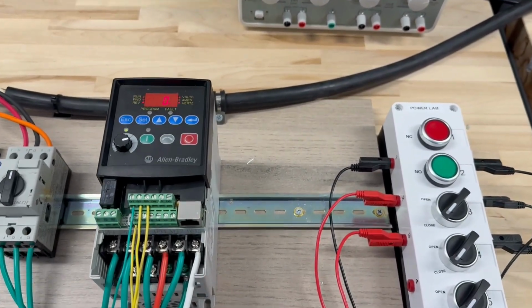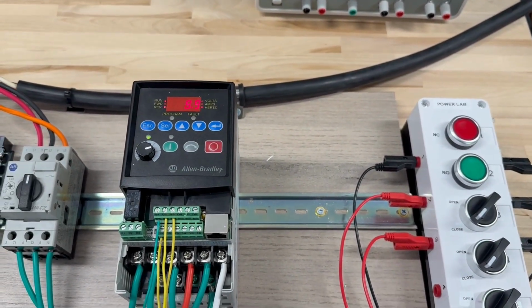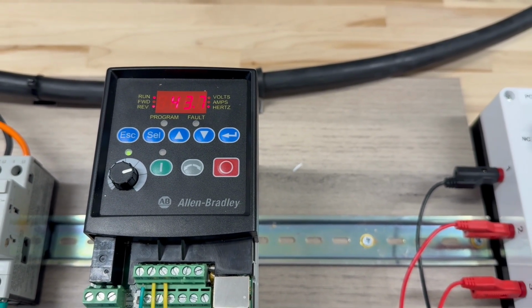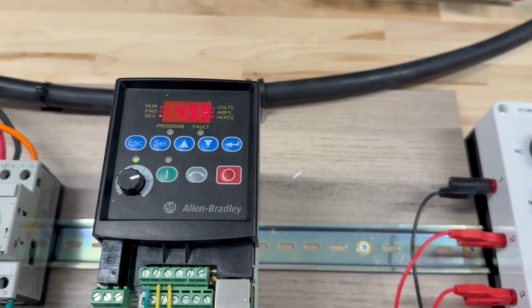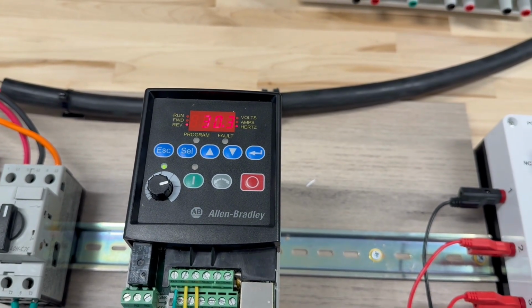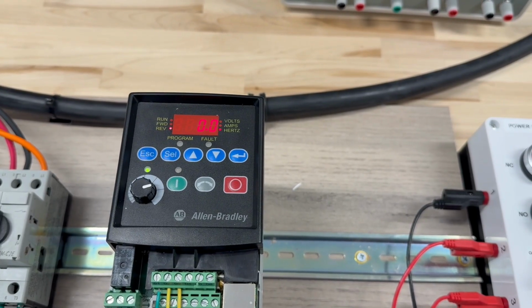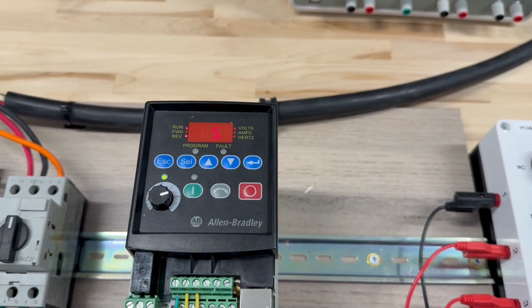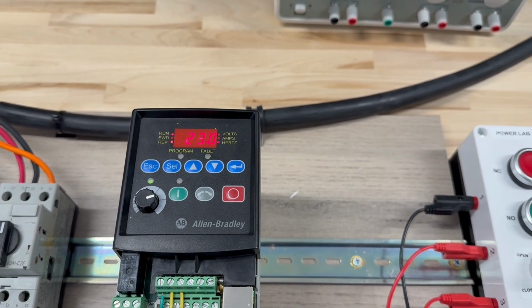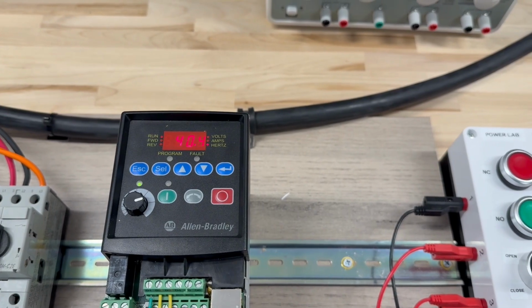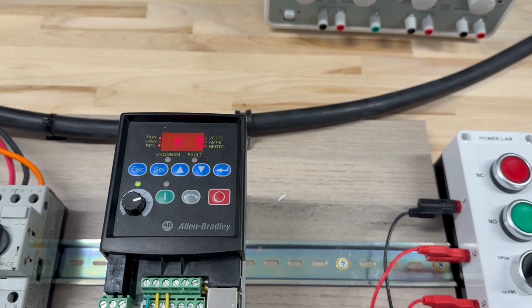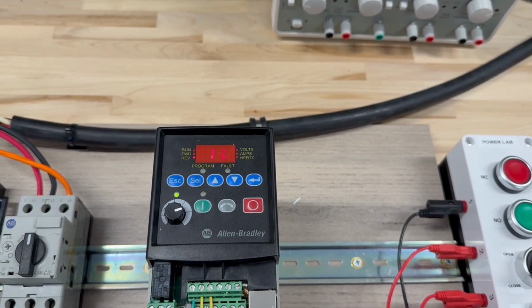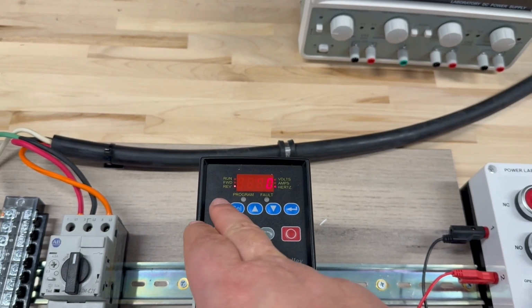As you see, I push the start button. See how the frequency change is fast and linear, right? That means the speed changes linearly between 0 and 50. Even when I take it off, see how fast it goes, and it's linear. The rate of change is not changing. The rate of the increase from 0 to 50 is exactly the same, which is linear, all the way from 0 to 50. Now let's stop it.